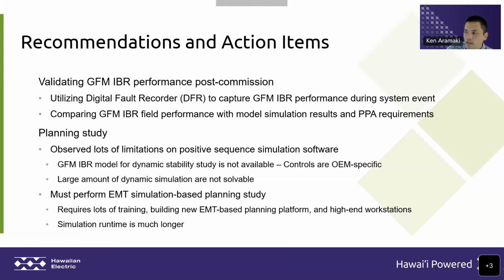And then in terms of planning studies, we did find limitations in the positive sequence simulation software. One of the limitations is that generally we don't have OEM specific grid forming models that can be used in the PSSE models. And also, PSSE wasn't able to capture all the issues on this really low or inertia-less system. And EMT modeling gives more confidence in identifying the issues.